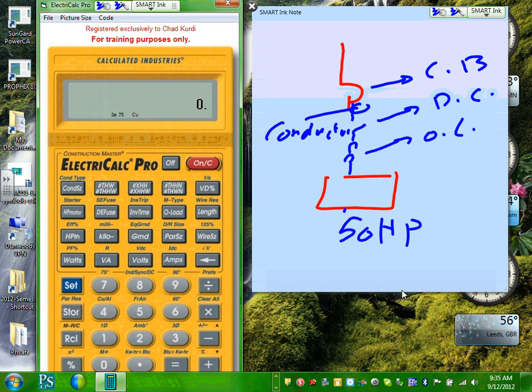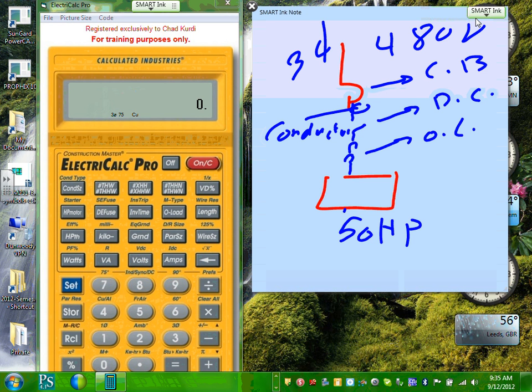What's the voltage system? Anybody give me a voltage system? 480. So this is a 480 volt, and it's three-phase, of course. Okay, so I have a three-phase 480 volt 50 horsepower motor. And what do I need to do? I need to size the circuit breaker, the disconnect, the overload, and the conductor right from the calculator. You're going to do this tomorrow with Chad by hand.